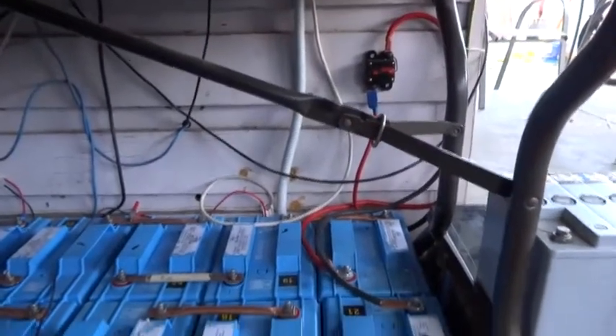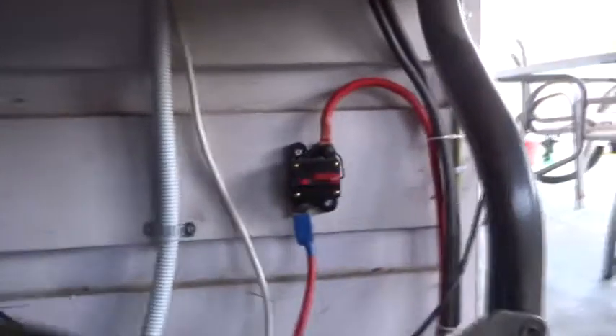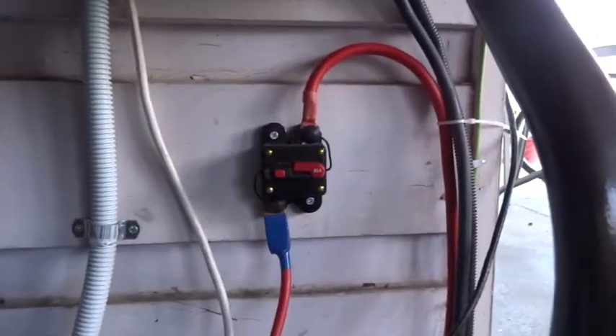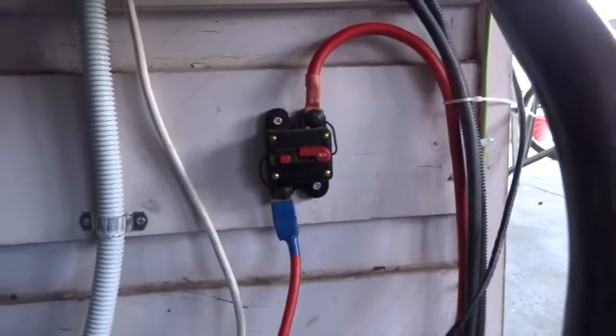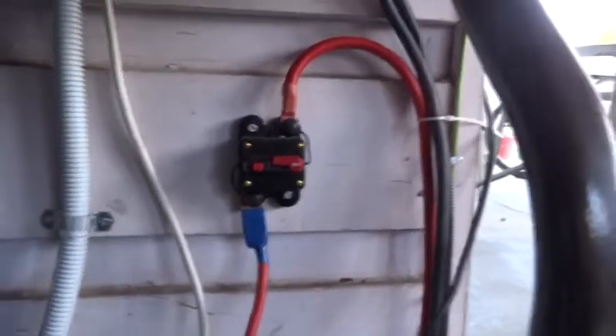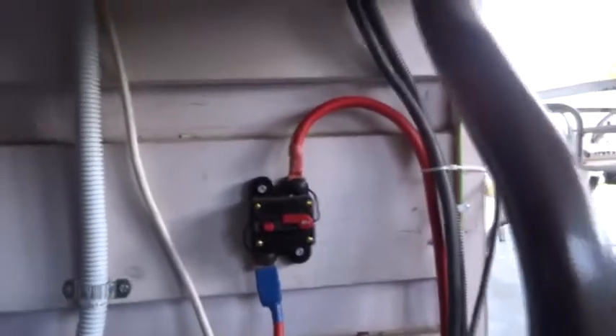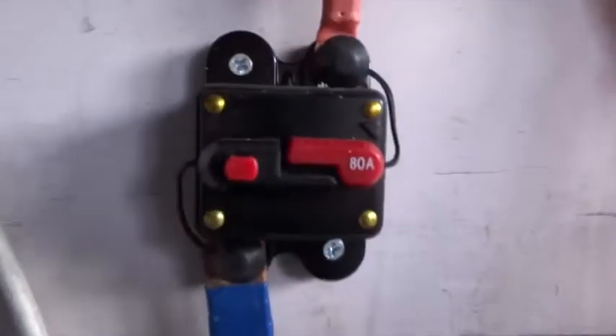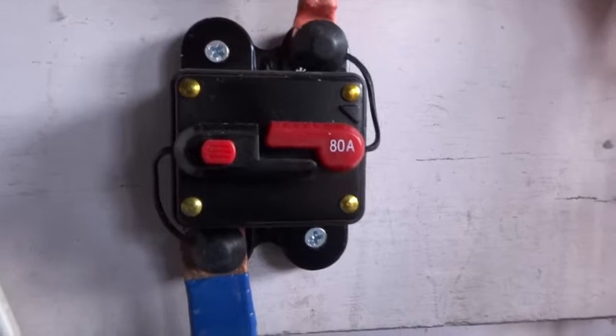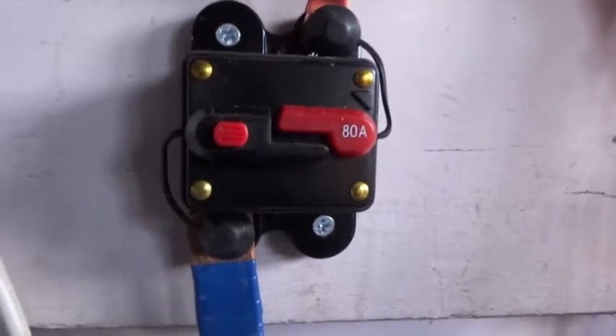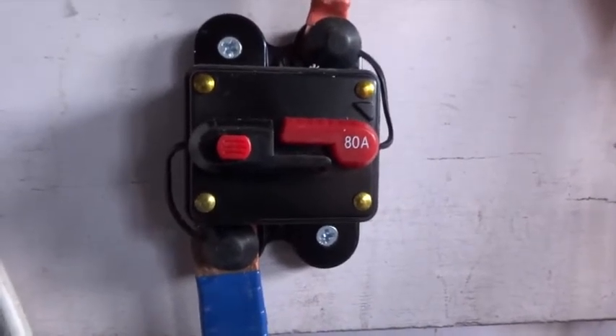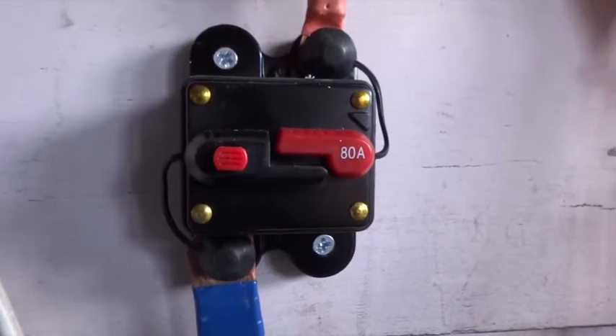This is the battery bank down here. On the wall here, between the battery bank and the solar panel, I've got a circuit breaker. I'm trying to work my way with the camera under the table here, so it's a bit awkward, but there's an 80 amp circuit breaker. The reason I've got 80 amp is because I needed to trip at a much lower amperage to protect the panel if anything goes wrong.